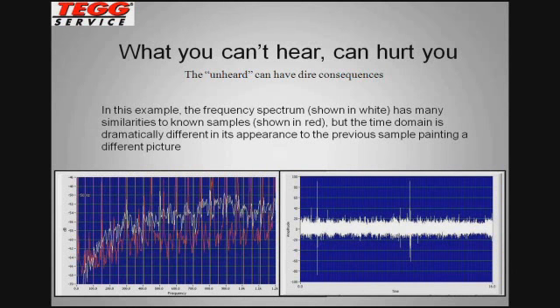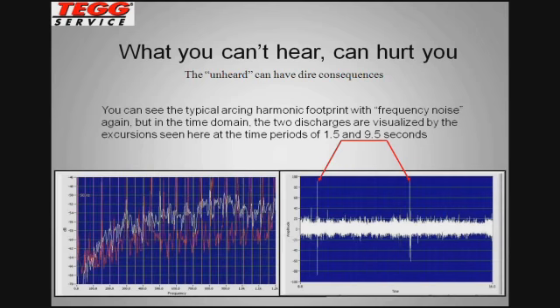There are several 50 hertz harmonics in the beginning of the spectrum, and very telling is the amount of frequency content or noise that appears in between each one of those harmonics. It is very busy, for lack of better words. So that's a tip-off that we want to look at something else, in particular the time domain. There we have that characteristic broadband of white noise through the entire length of the recording. That should be normal for a transformer in this case. But you see 2 distinct excursions there, and I'll switch to the next slide, that coincide with what was heard and recorded within the instrument.